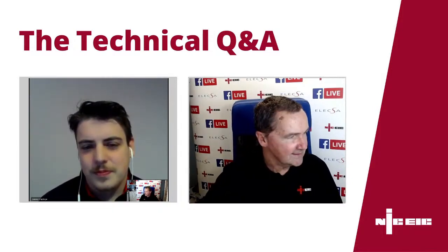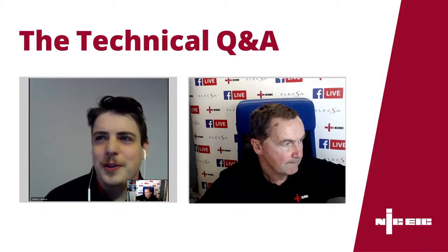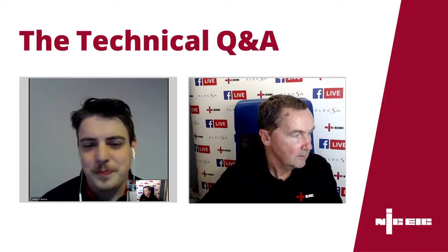Would you add anything to that, James? Again, that's what I was alluding to about ongoing accuracy: using a known source and regularly checking throughout the year. I'm assuming that you're interchanging the leads and it's still doing it. So in that case, it looks like there may be an issue with the tester, I'd say. Yeah, in some form. Okay.